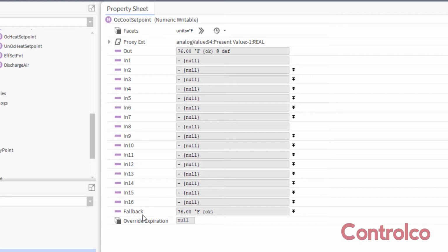In the real world, if you allow your customers to use the set action on things like dampers, this fallback priority is higher than any priority in the field controller, and the field controller sees this as an override. For example, if this was a damper and I overrode it to 0 or 100%, there's nothing in the field controller that will allow it to change that.